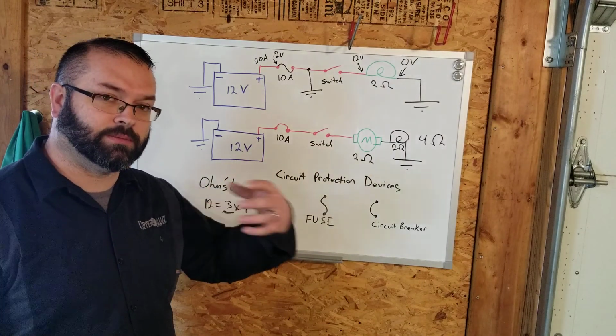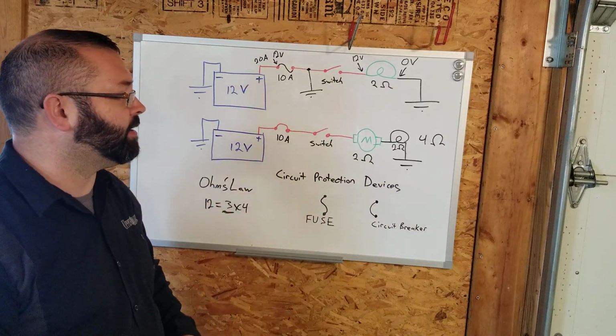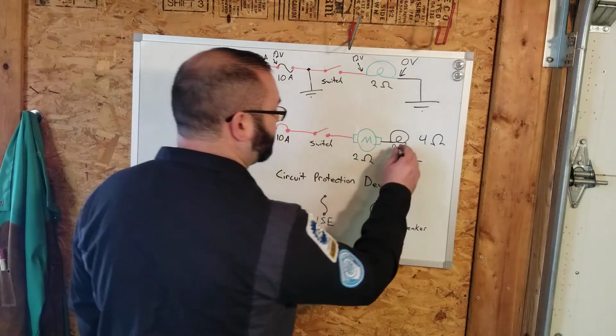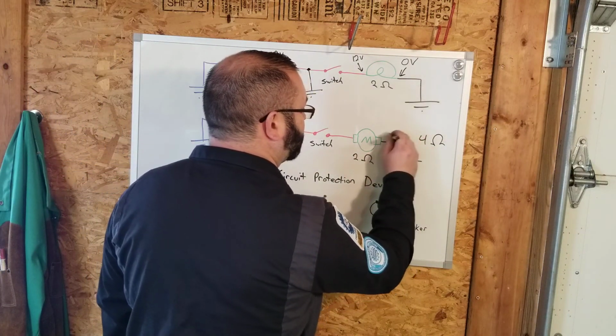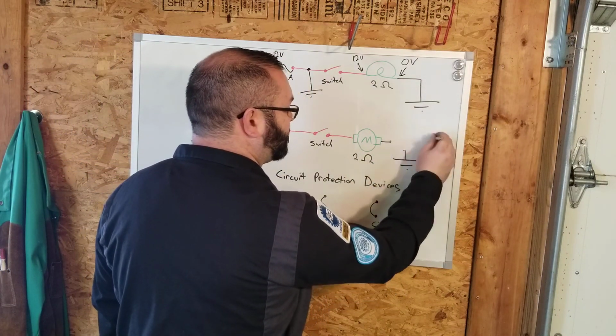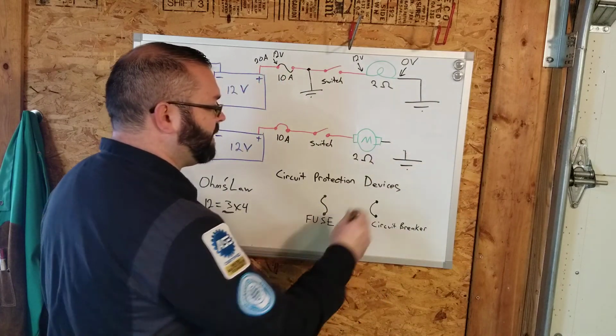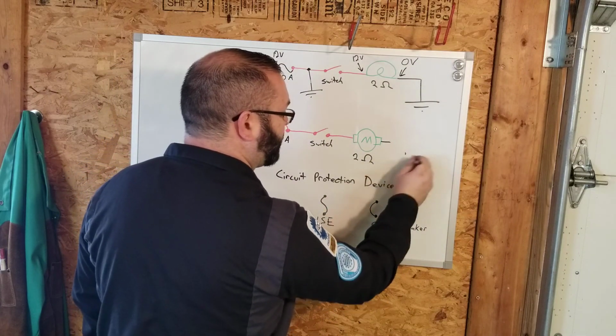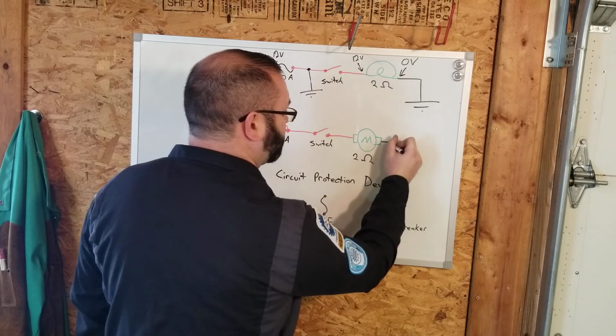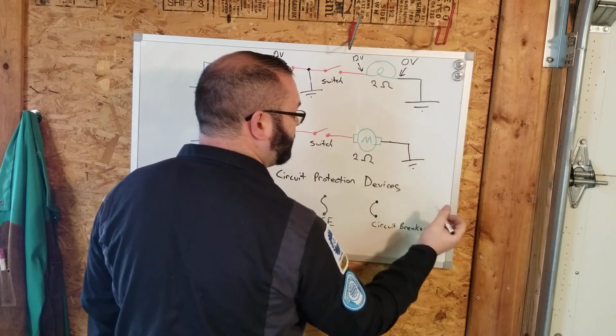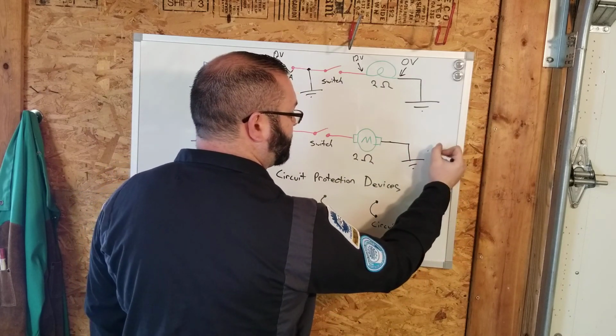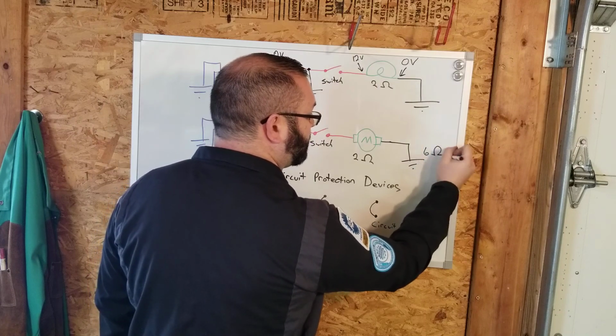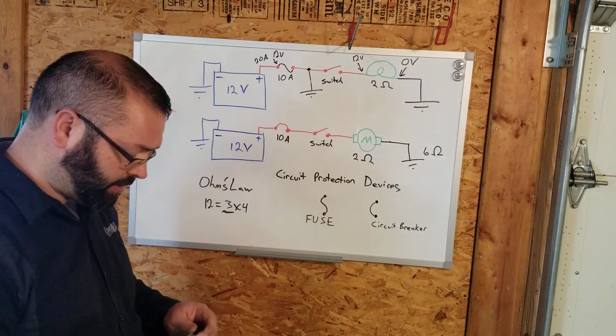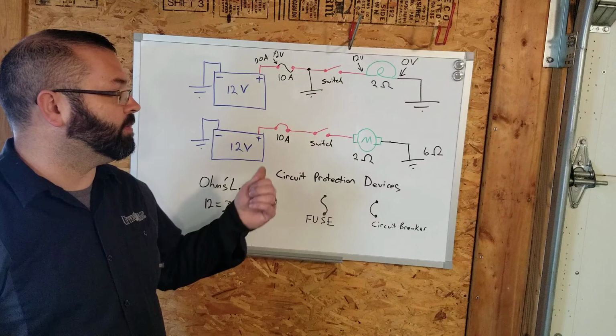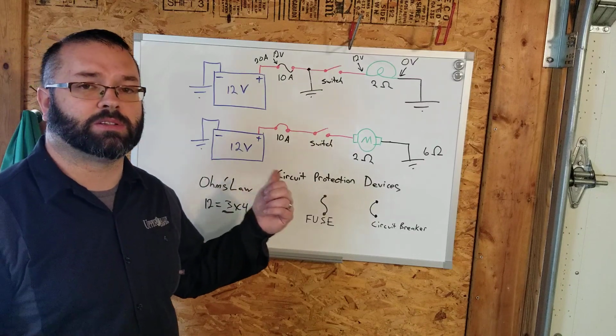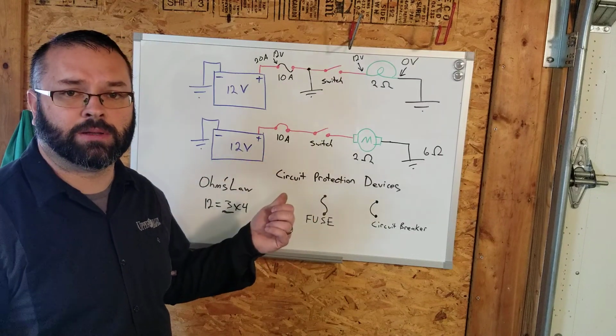This can also happen another way - let's say it wasn't a light bulb. You know I despise rust and corrosion, but if we have a corrosion issue at our ground, say 6 ohms of resistance at that ground, that's going to slow amperage down a lot. This motor's going to spin slow, and if it's a light bulb, it's going to be dim.